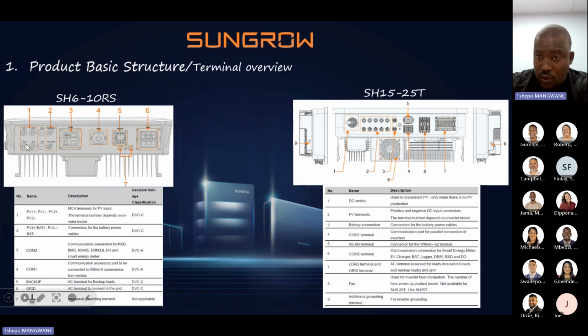It's rated as a 32 amp MPPT. Per string is 16 amp. Okay, maximum startup voltage on this system, it's 40 volt. Then max, it's 600 volt per string. All right. And also not to forget to mention that these are high voltage inverters.